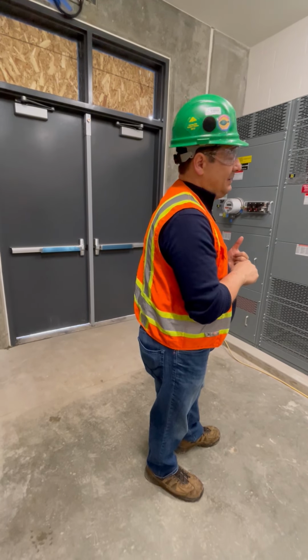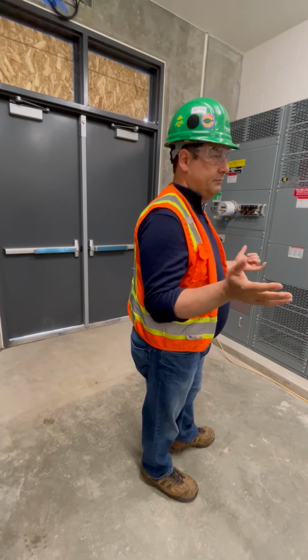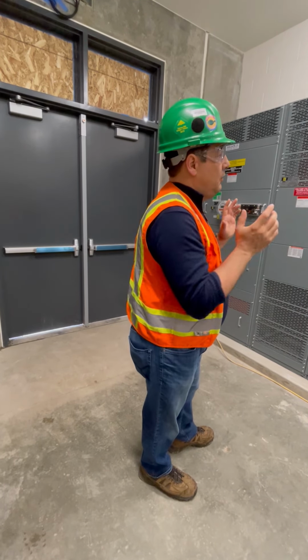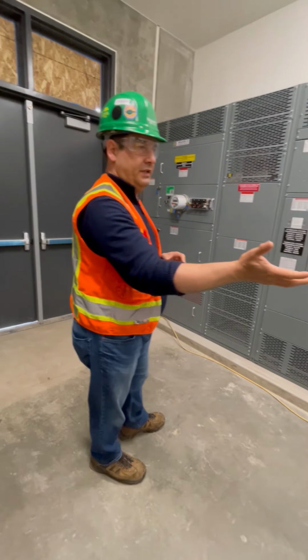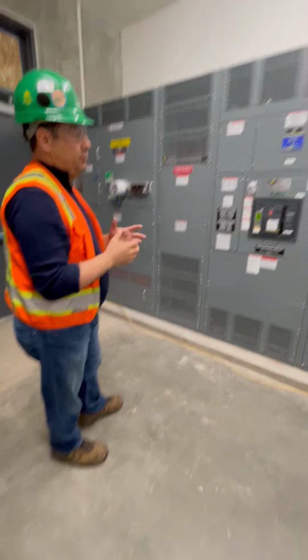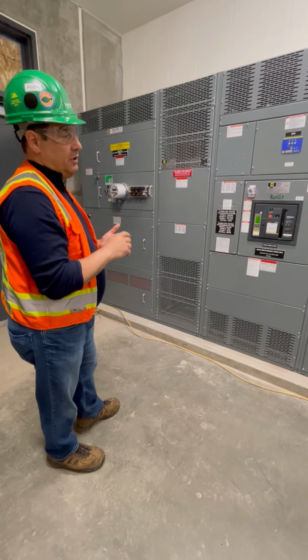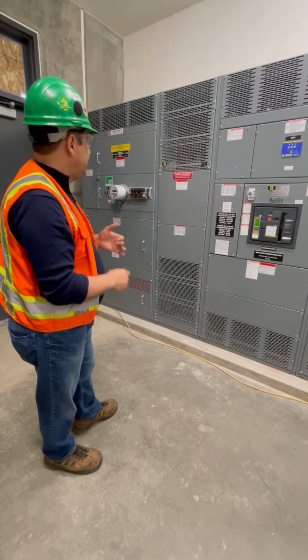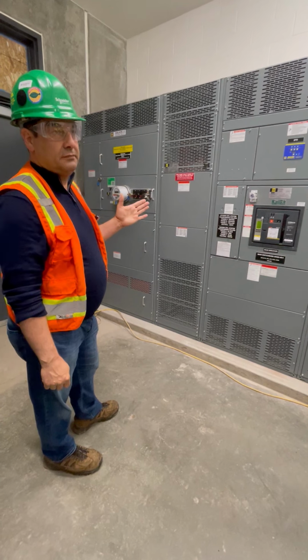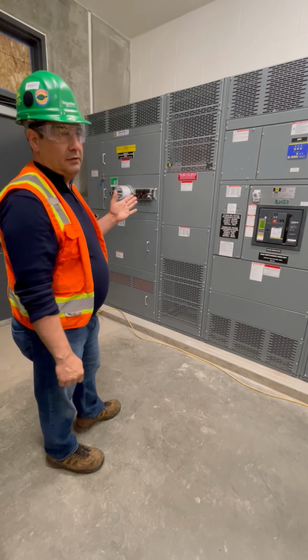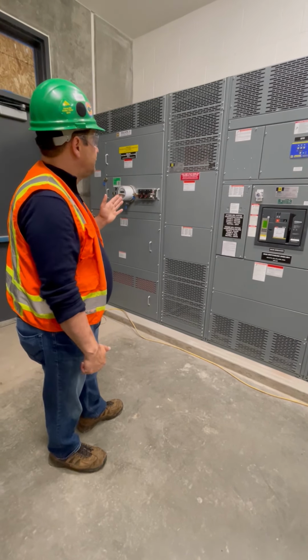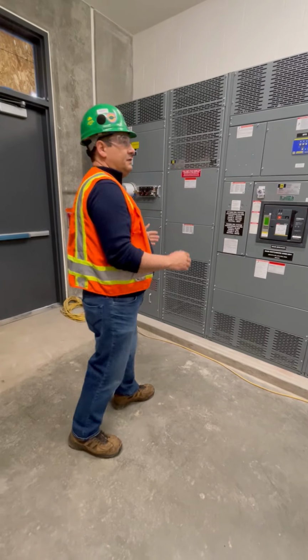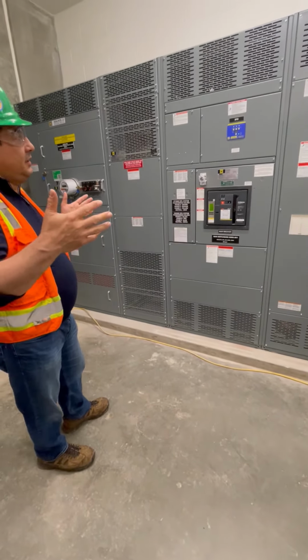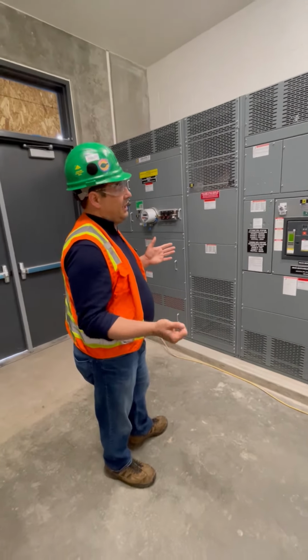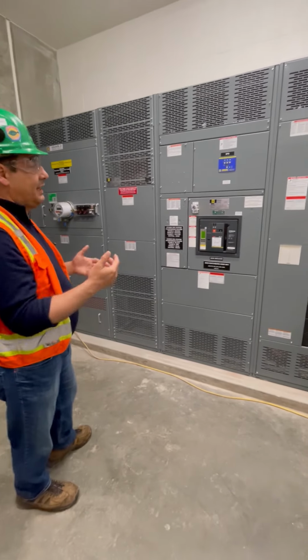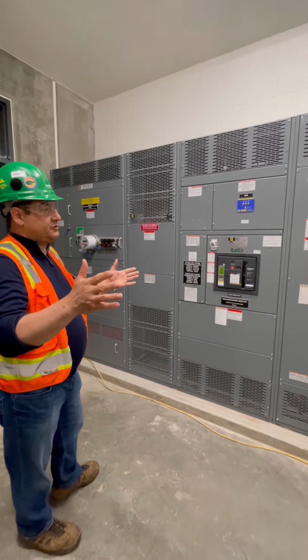On the maintenance side, we recommend as a manufacturer that you do some form of maintenance once a year. Most customers don't do it. That's up to you. Once the switchboard comes out of warranty, it's really your responsibility. It's your product, right? But we do recommend maintenance once a year for good operation and reliability. What that means is you open it up, go through it, and check every termination and connection. You look at debris and clean the debris out as well. In this particular case it's a very enclosed, ventilated room, so you don't have a lot of debris flying in here. But that's why we recommend cleaning it once a year, because we cover all the environments that these switchboards operate in.